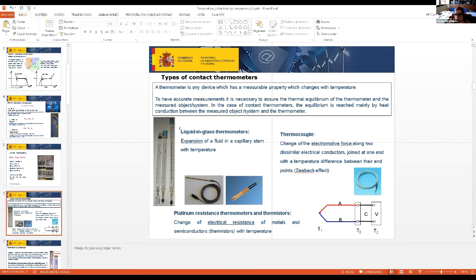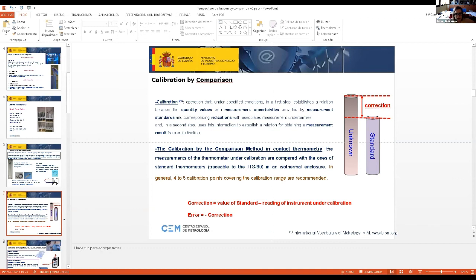We have liquid-in-glass thermometers, which use the expansion of a fluid in a capillary stem. The thermocouple is just the generation of an electromotive force between two different wires when the ends of these wires are at different temperatures. And maybe you know better the resistance thermometers, which can be platinum resistance thermometers and thermistors. In this case, the property that changes with temperature is the electrical resistance. But here we want to talk about calibration by comparison.